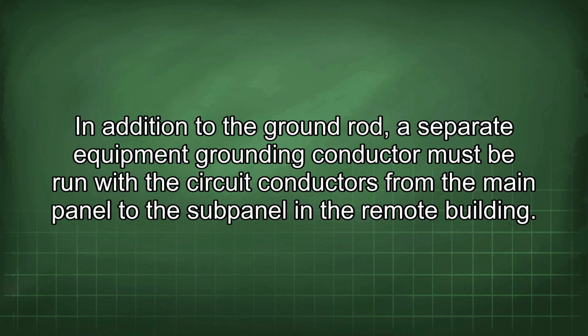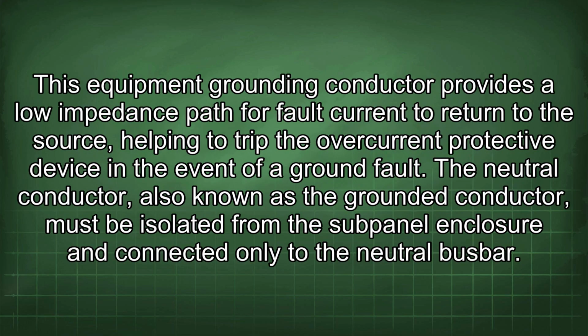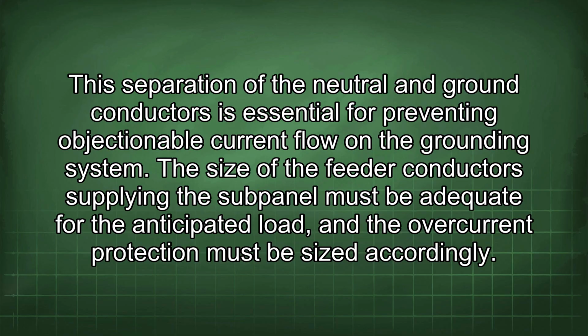In addition to the ground rod, a separate equipment grounding conductor must be run with the circuit conductors from the main panel to the subpanel in the remote building. This equipment grounding conductor provides a low impedance path for fault current to return to the source, helping to trip the overcurrent protective device in the event of a ground fault. The neutral conductor, also known as the grounded conductor, must be isolated from the subpanel enclosure and connected only to the neutral busbar. This separation of the neutral and ground conductors is essential for preventing objectionable current flow on the grounding system.